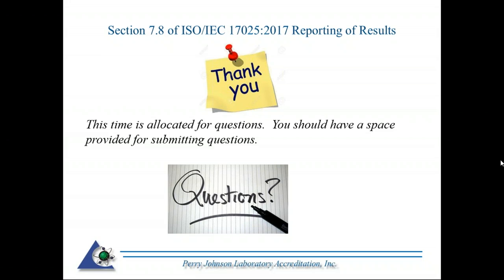You can look at that many ways. If it needs to be traceable, it needs to be calibrated if it's directly related. If you're using something like a check standard, where we mentioned you have something calibrated, or something that's out of your control, and you have it back and you have something that you can compare it with, and I'm assuming that because of the clause you have referenced there, it's out of your control. As long as that initial traceability is intact, you have a traceable calibration, you had it checked, and then it's out of your control, and then you use it again.